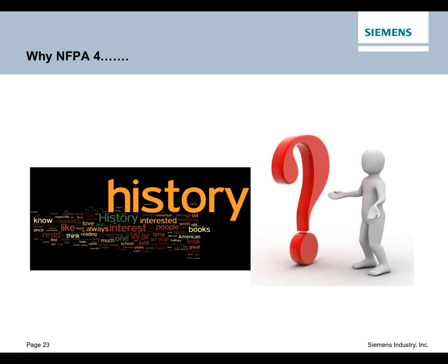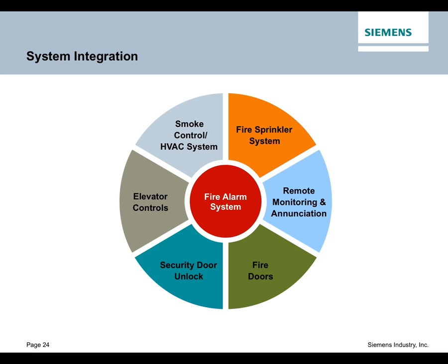So what that has led the industry to is the creation of NFPA 4, which is the standard for testing of integrated systems. It's the testing from end to end. It's the testing of when that smoke detector goes off, how it activates the fire alarm panel, how that fire alarm panel sends a signal to the HVAC controller to close a damper, to the elevator controller to recall elevators, to maybe unlock some stairwell doors, and those types of things. Those kinds of functions are now in what they call integrated testing.